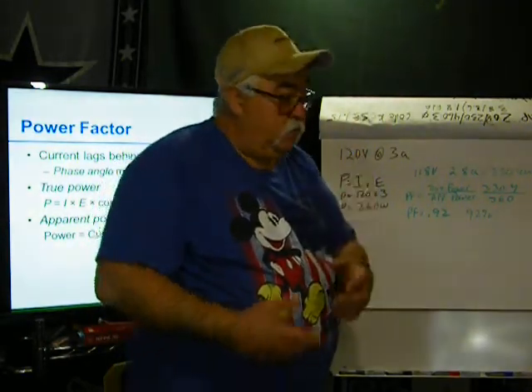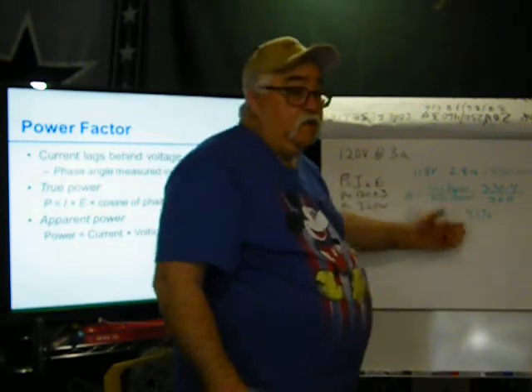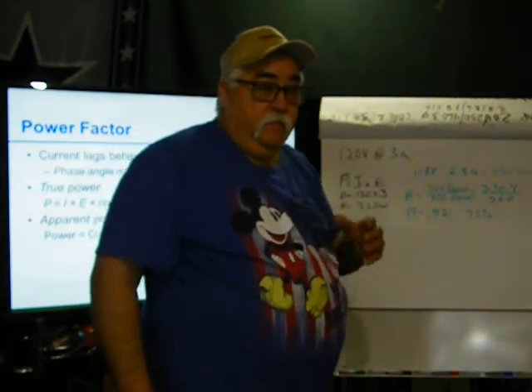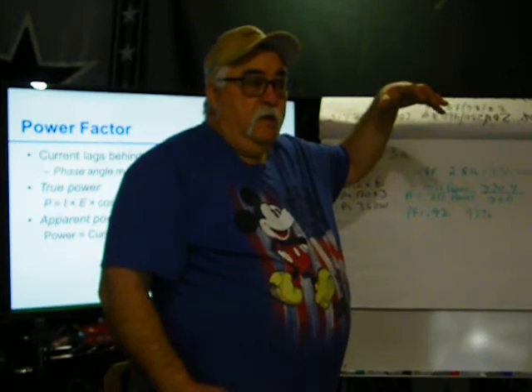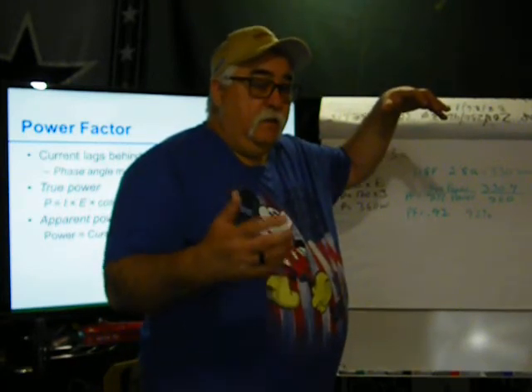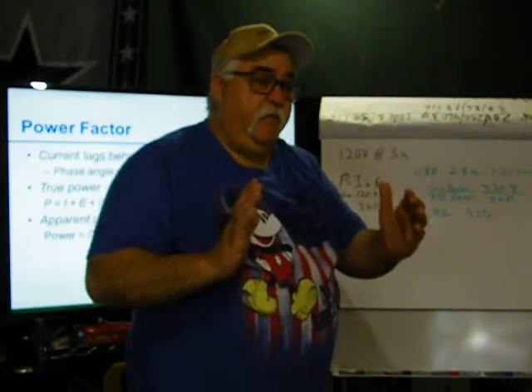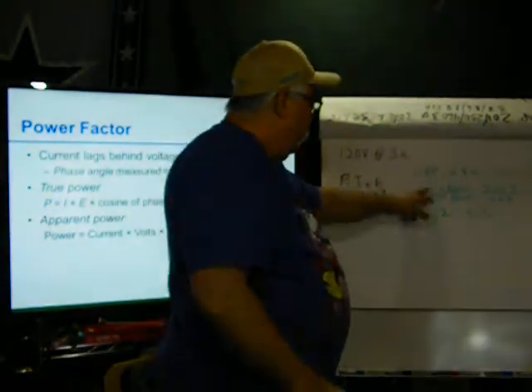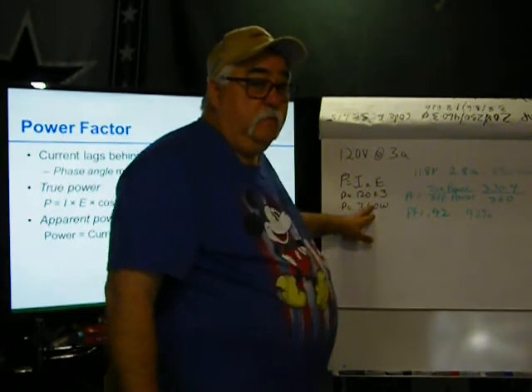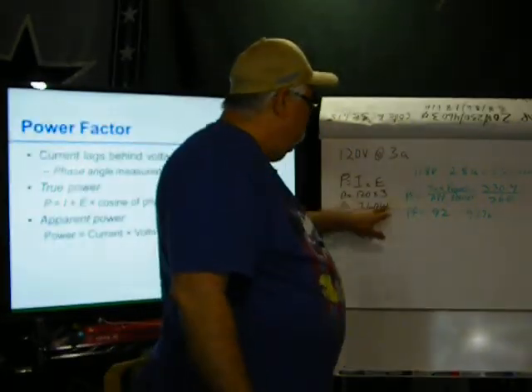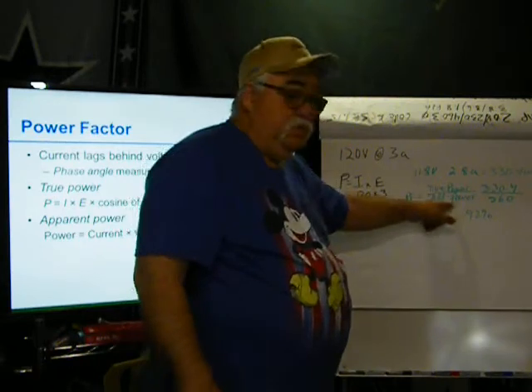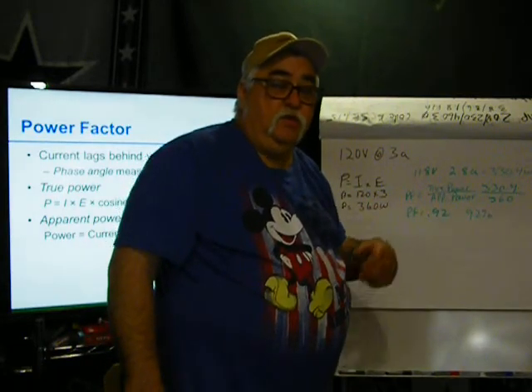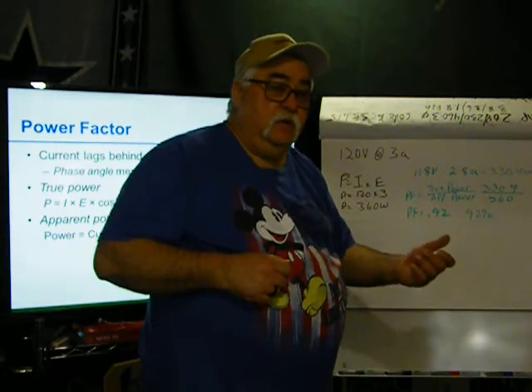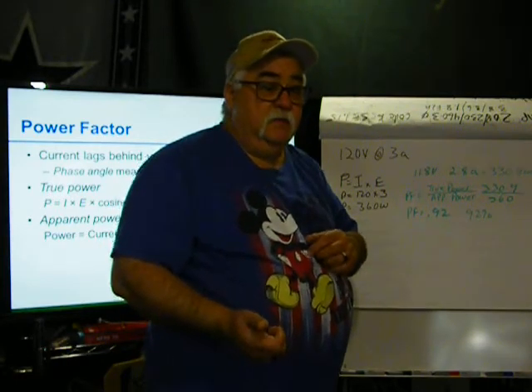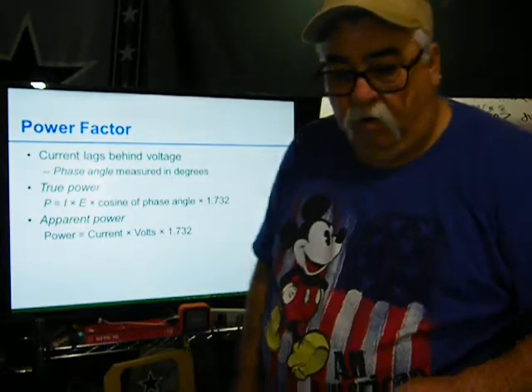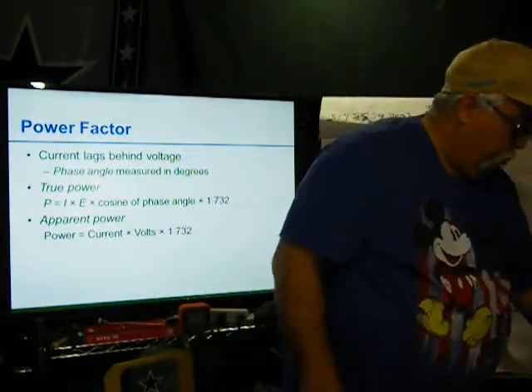Okay, I'm talking about one load. You get an area that has multiple loads, and this will add up. All of a sudden, they're producing more electricity than what you're using for you to pay, because that power has to be available. If this went up to 100%, this has to be available for it to work. So the utility is producing more, so you can use less and pay for less. So they're losing money. So that's why power factor is an important part.